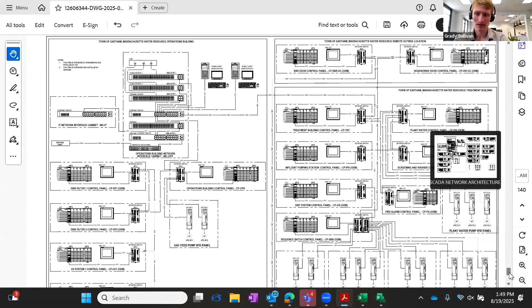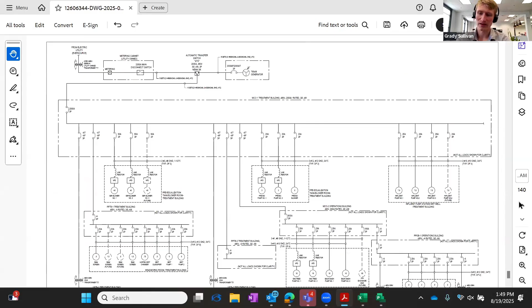The upside of that is if we were to lose the Ethernet connection between, say, the treatment PLC and the plant water control, for instance, you wouldn't lose access to that on the SCADA system or rest of the network, because you have another way - if you loop back around the other way - to basically get that information on the network. So you'd have to have two severed connections for that to actually be a problem.